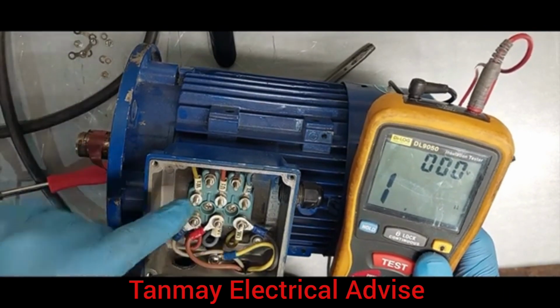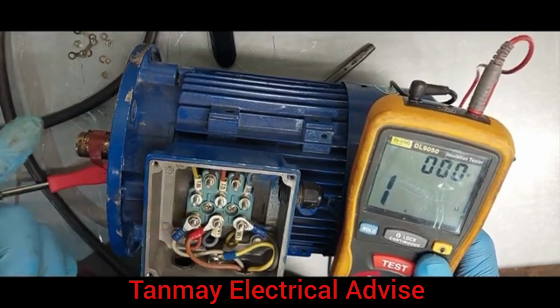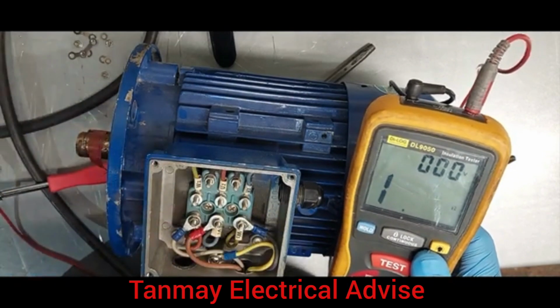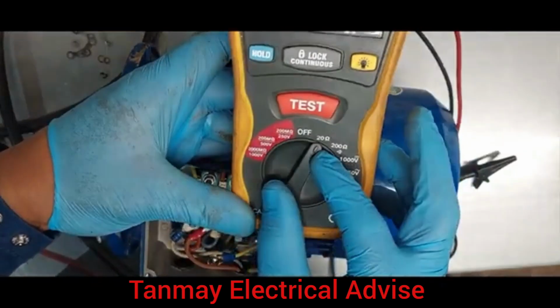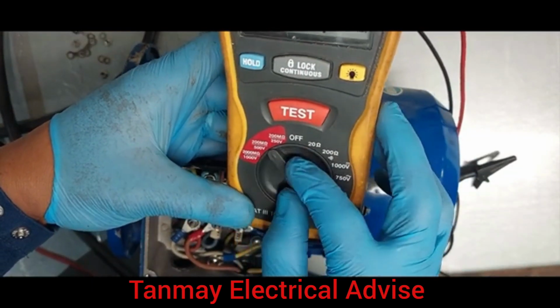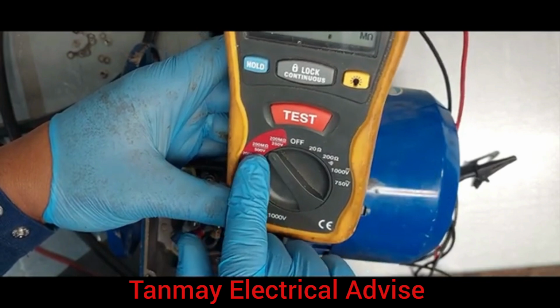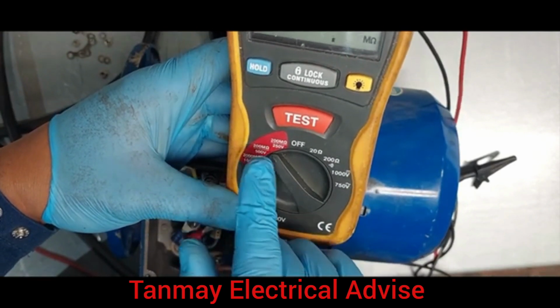So what we do is inject 500 volts, and we have to look to see that it returns between 1 mega ohm and 2 mega ohm. This is the reading we're going to get. So we can test, we can inject now. We put it to inject 500 volts here.